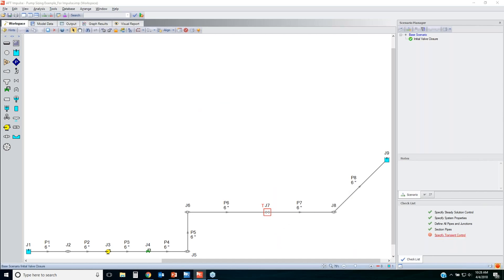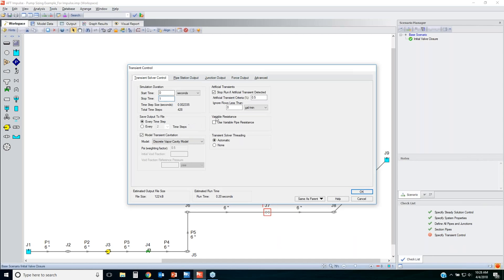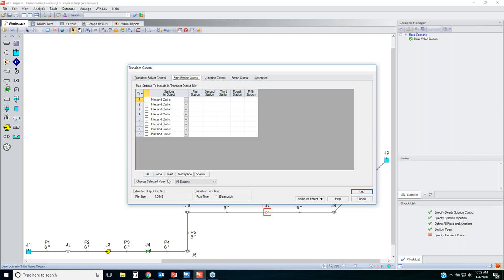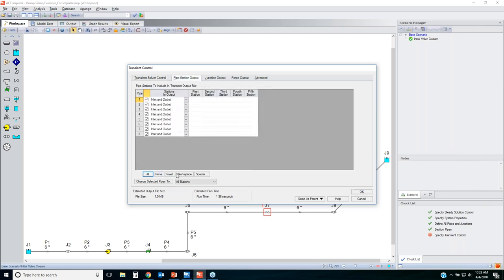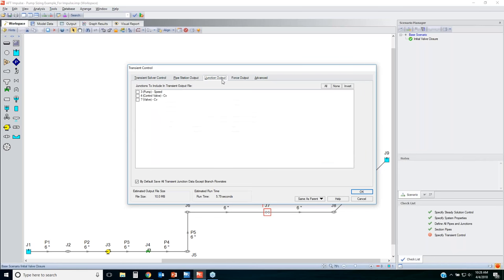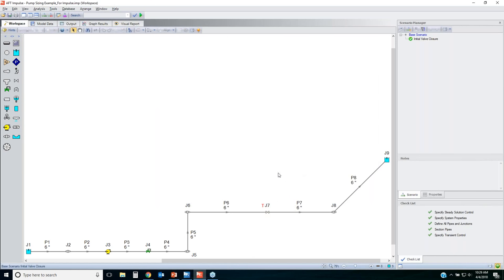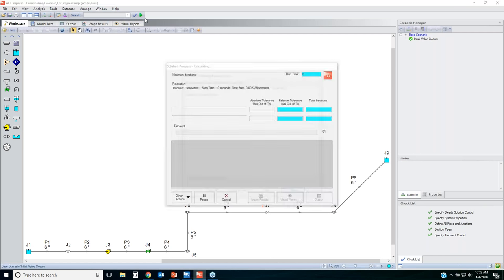Now I'll specify my transient control. Since I'm closing the valve in one second, I want to see what happens in the first 10 seconds of the simulation. I'll use the default cavitation model first, save all piping stations for results, and save my junction data. Now I've got all green check marks and I'm ready to run the model for the transient analysis.